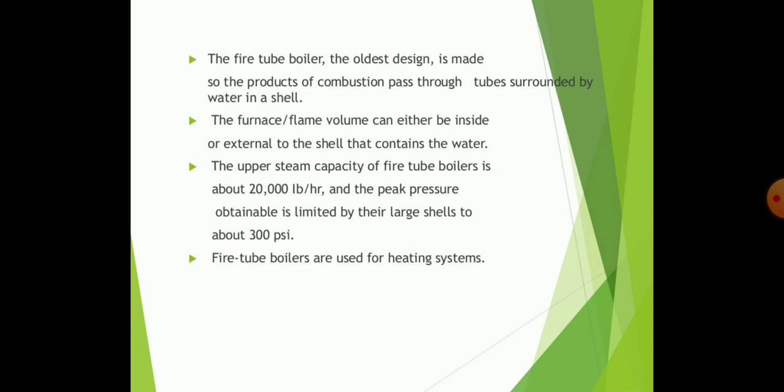Fire tube boilers are the oldest design, made so that the products of combustion pass through tubes surrounded by water in the shell. The furnace flame volume can be either inside or external to the shell that contains the water. The upper steam capacity of fire tube boilers is about 20,000 lb/hr, and the peak pressure obtained is limited by their large shells to about 300 psi. Fire tube boilers are used for heating systems.